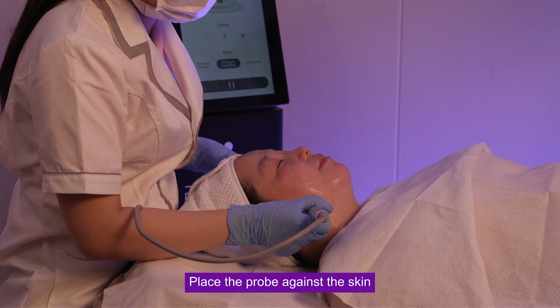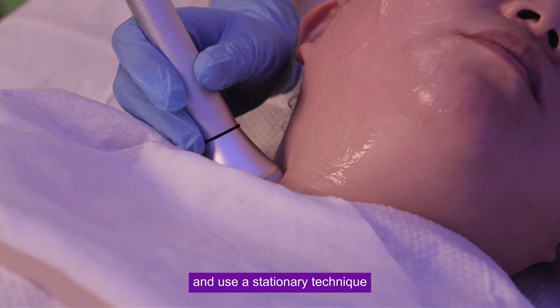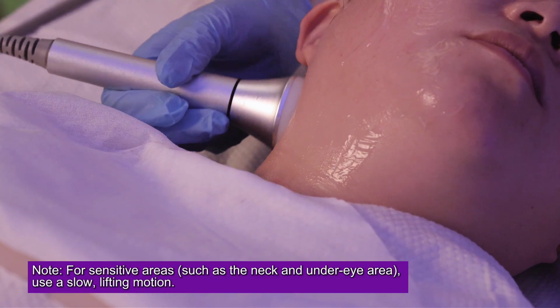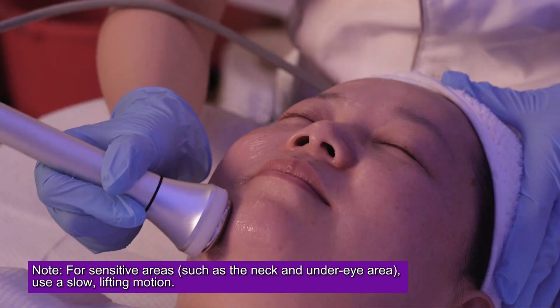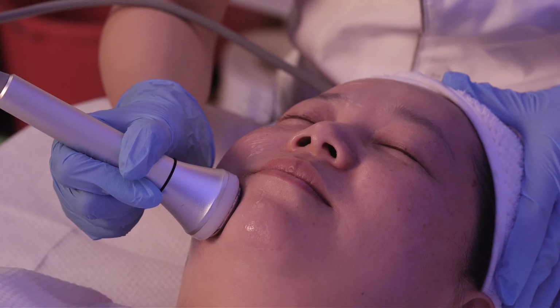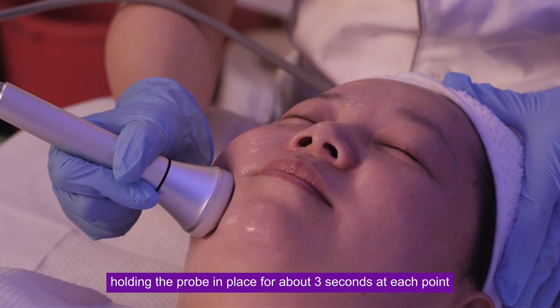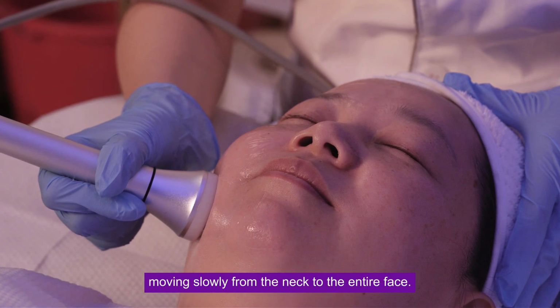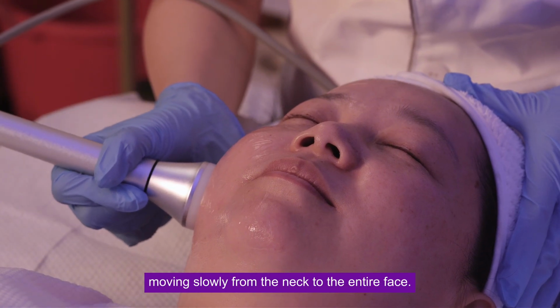Place the probe against the skin and use a stationary technique. Note, for sensitive areas, such as the neck and under-eye area, use a slow, lifting motion. Holding the probe in place for about 3 seconds at each point, moving slowly from the neck to the entire face.